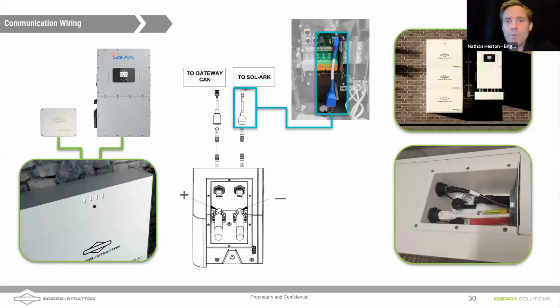We mentioned that our batteries communicate with the Sol-Ark. The 6.6 battery communication wiring is showing here. It's a fairly simple connection. If you're using our Energy Track gateway in order to monitor individual battery modules, you would connect that through the RJ45 port. So we just have 2 RJ45 connections. That's an Ethernet sized connection. And then that CAN bus port on the battery controller will come through a dongle and go directly into the Sol-Ark. And that dongle is provided with that controller, comes in a bag inside that controller box. And so it's fairly easy wiring. It's just a direct connection into the Sol-Ark battery communications port there.